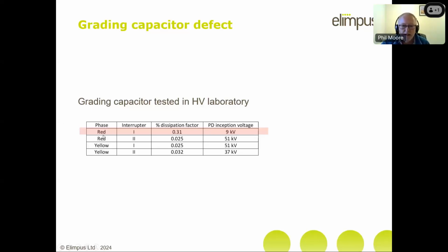And you can see that for this red phase interrupter 1, the PD came at about 9 kV, whereas for all the others it was way above, not less than 37 kV, so very, very different. There's also what's called the dissipation factor, which tells you about the current that flows into the grading capacitor. It should really be exactly at 90 degrees to the voltage. It tells you whether there's any slight phase angle in that, because any slight phase angle means that the current going into it is actually producing some heat. And you can see again that this red phase interrupter had a very high dissipation factor. So pretty much a smoking gun there, very conclusive proof that there was an issue.